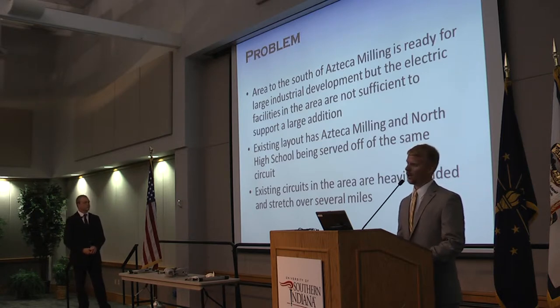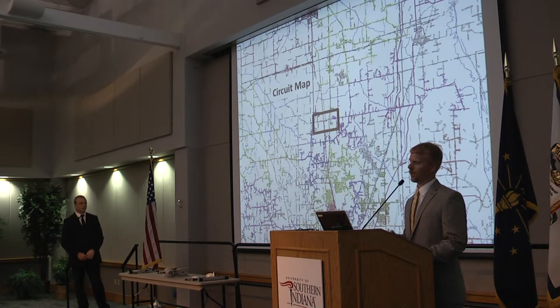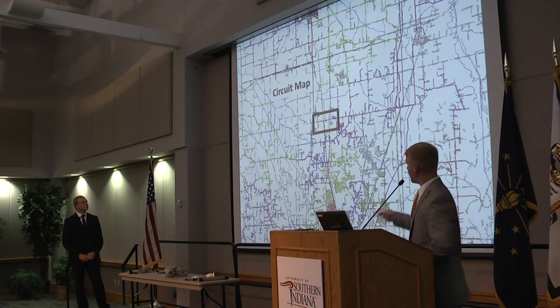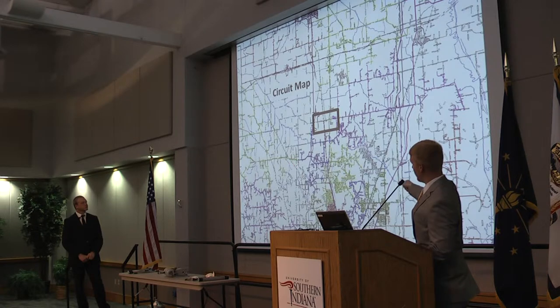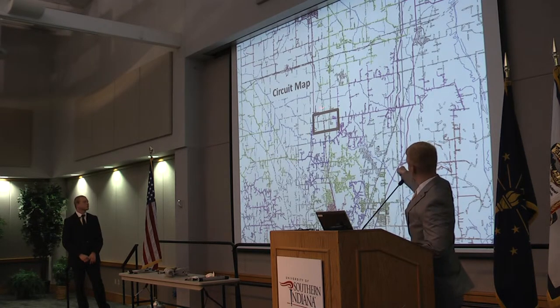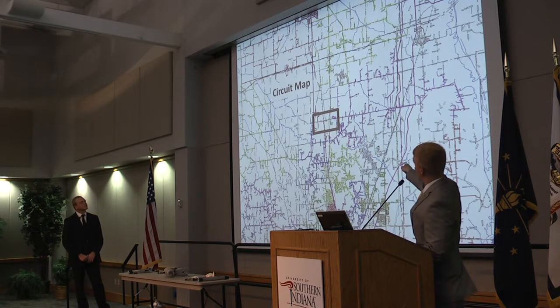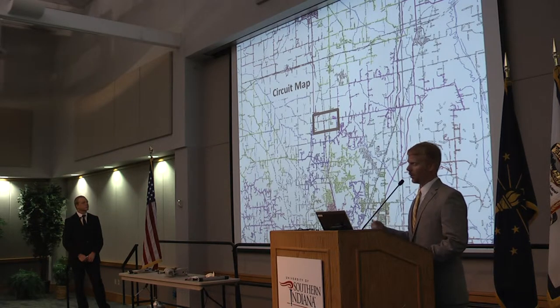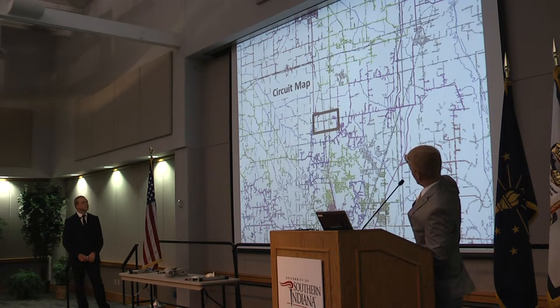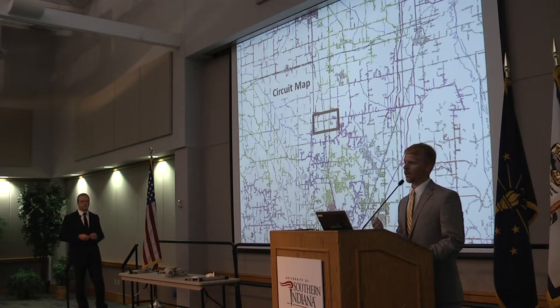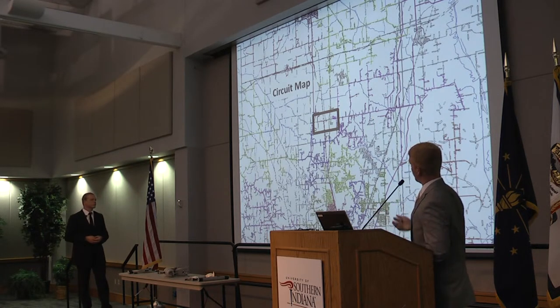Also, the existing circuits in the area are heavily loaded, and they stretch over several miles, which can be seen in this next picture. This is a GIS circuit map. This is the system that Vectren uses to map all of our systems and our facilities in the area. This is just a very zoomed out view of all of the different circuits. Each color represents a different circuit. As shown here at the bottom, this is a very dense area as you go further south in Evansville. As you look here, this is our actual area, the boxed in. The substation is located here, and in this area are the two circuits that come out of Azteca Milling right now. The large circuits that we're talking about can be seen in the pink and the green. So what we're hoping to do is provide more capacity that we can pick up and actually feed some of this area so that it can be relieved off the other circuits.